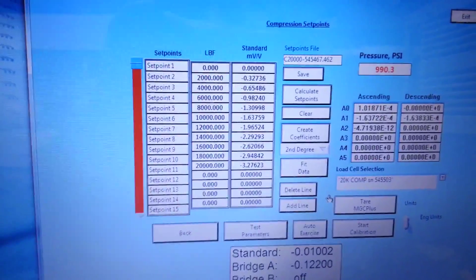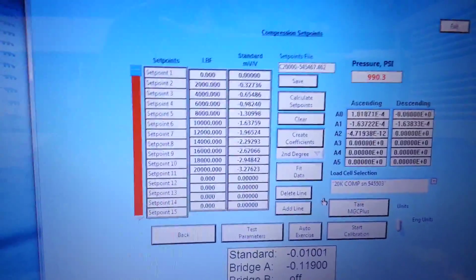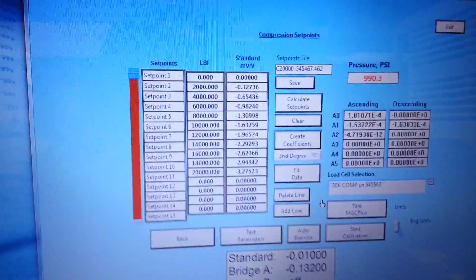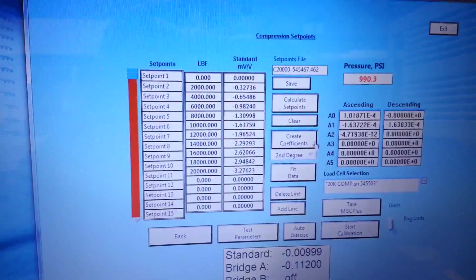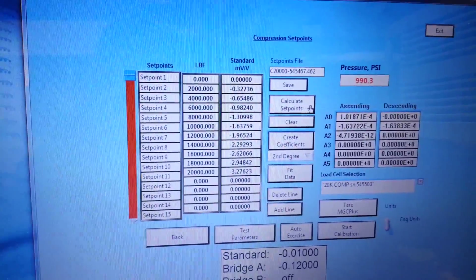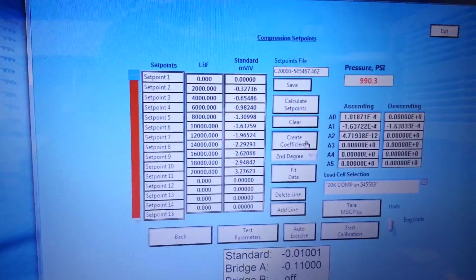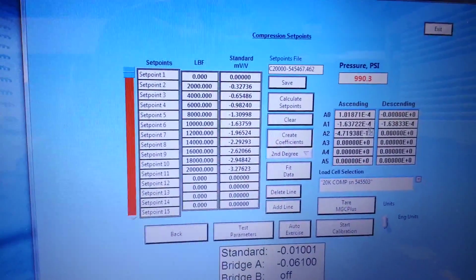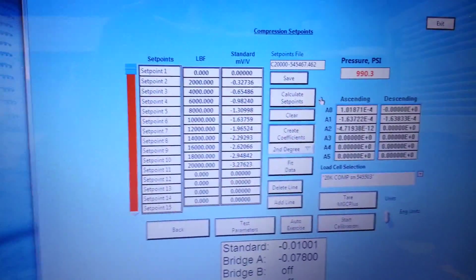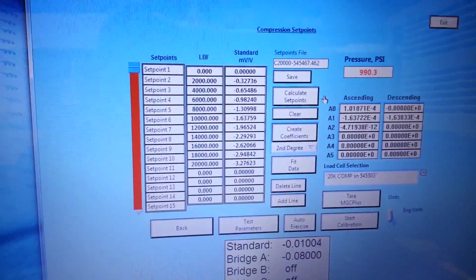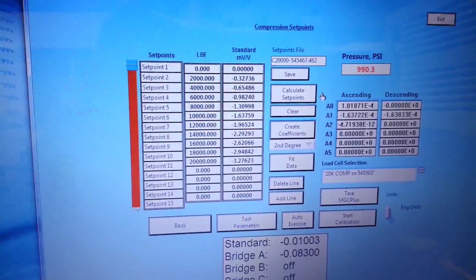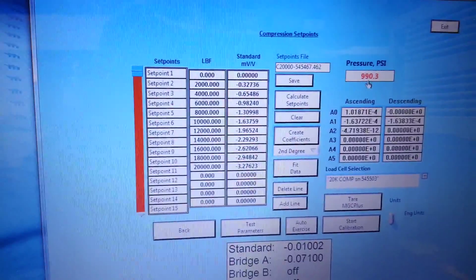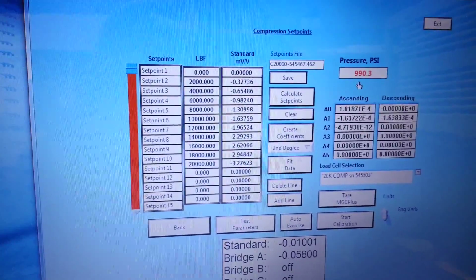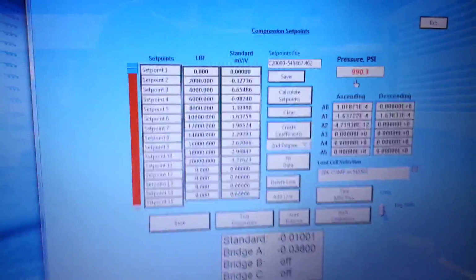I selected the table that I already created using the coefficients from the test report. After that, I click here on calculate set points. First of all, I create the coefficients, which are these numbers right here, and then I calculate the set points by inputting the test points that I want them to hit. The regulator is supposed to be set at 990.3, so I set it up around 1000.